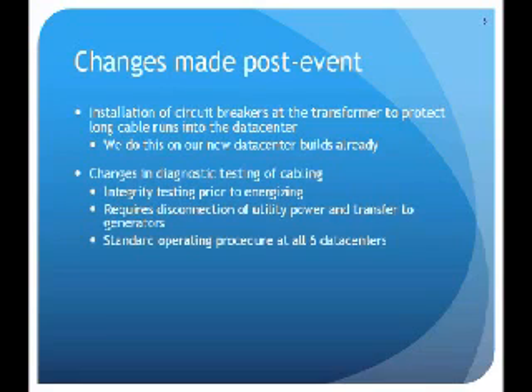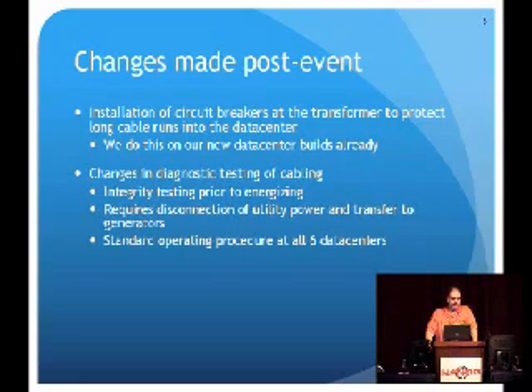We've changed some of the diagnostic testing of the cabling itself. So we do some integrity testing prior to energizing the cable, and we also do it as part of our regular maintenance. We have to actually disconnect from utility power and transfer to generators, and this has become standard operating procedure in all of our data centers now.